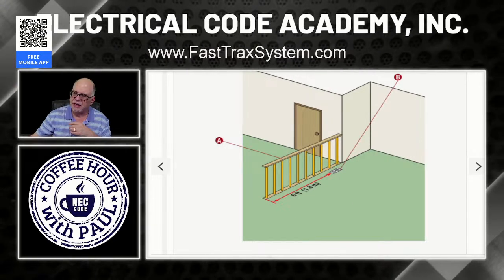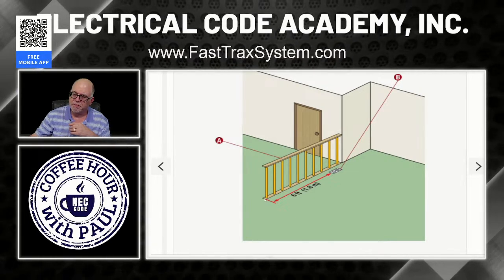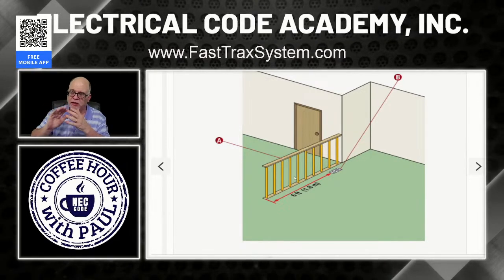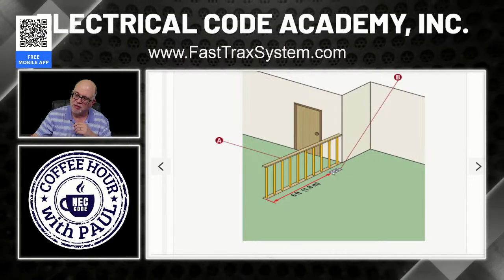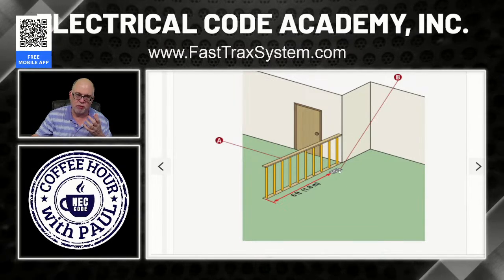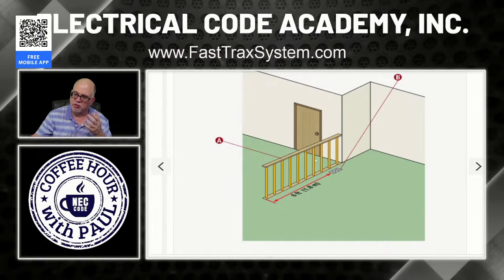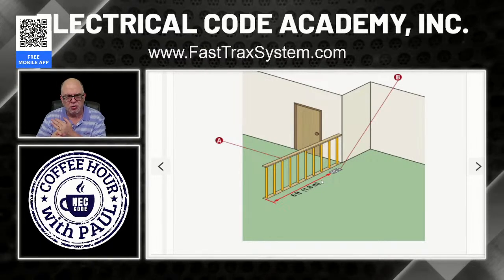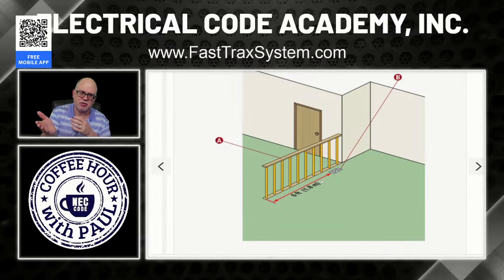But in this case, if you look here, here's the end of that wall, or in this case, bar. But if this was a half knee wall with gypsum on it, just like these walls over here, then it would still be a wall, and so it would still apply. From the edge, you come in and it can't be more than 6 feet right there. Now, we're obviously not going to put it up in this railing, so that's why this one's on the floor. But if this was gypsum board and this was a half wall, a knee wall, or whatever it was, then you would expect it to be mounted in the wall. But could it be in the floor? Absolutely, as long as it's not more than 18 inches. Now, the cost factor to do this is probably, in this case, it's the only thing you could do because, again, it's rails.